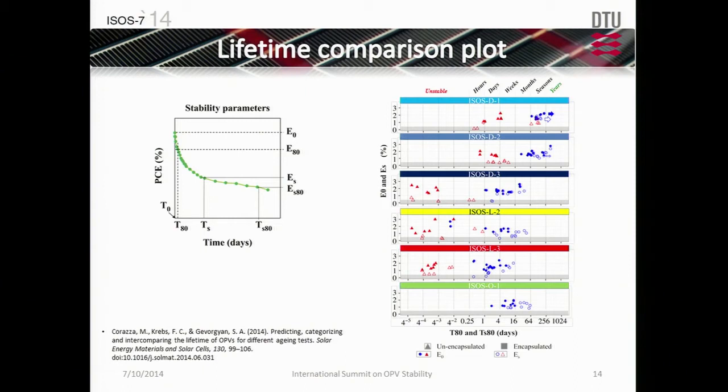And it is possible with this kind of plots not only to relate this indoor test, but also to have a look at the outdoor data. I encourage you to use the same kind of plot, because we want to have more and more data points in this type of graph, because finally we would like to use this as a tool for lifetime prediction. And we are still in an early stage. However, the idea is that you will perform a fast and harsh test, and that looking at the ratio among the different tests, you can try to predict the lifetime with a certain uncertainty, of course.